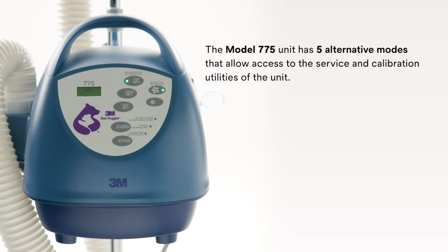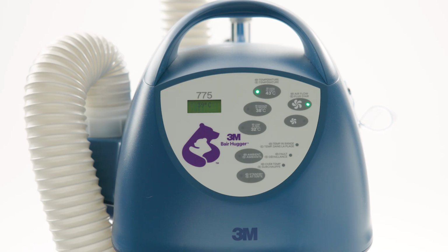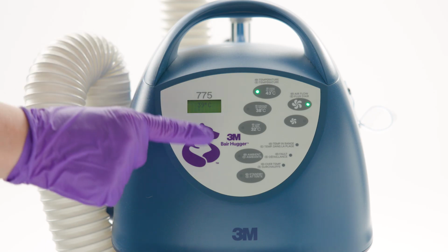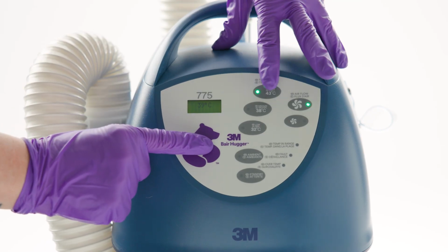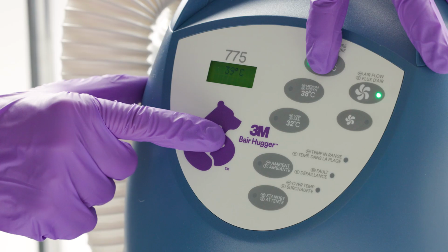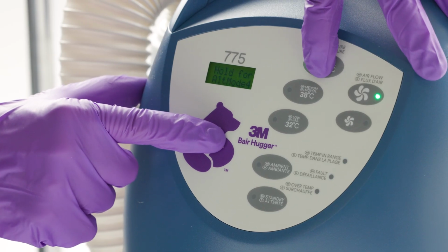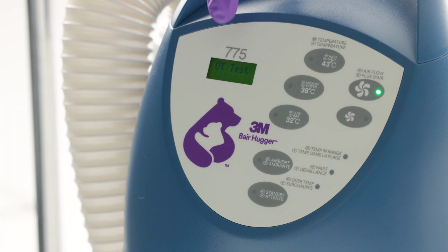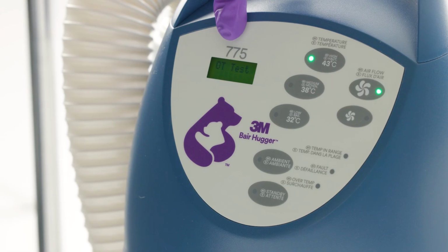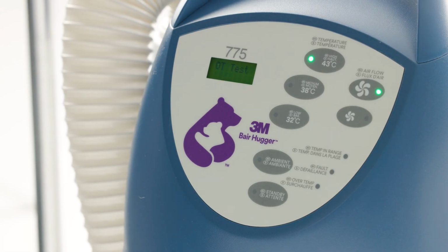The Model 775 unit has 5 alternative modes that allow access to the service and calibration utilities of the unit. To access the alternative modes, press and hold the Bair Hugger logo in combination with one of the operating mode buttons located on the front panel. Each combination accesses a different service or calibration mode. Service technicians can reference instructions located in the preventative maintenance manual. Exit the alternative modes by pressing the Bair Hugger logo on the control panel or by waiting 60 seconds.